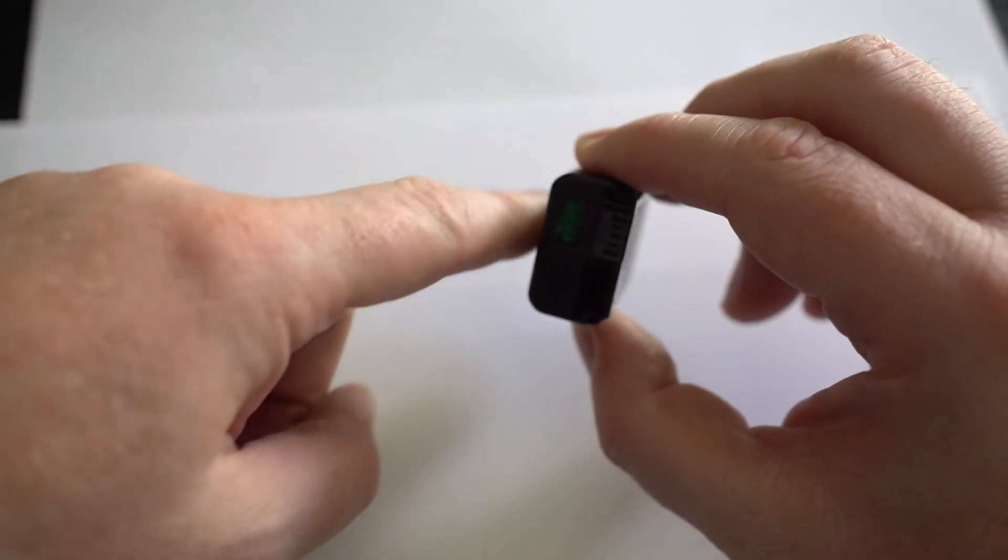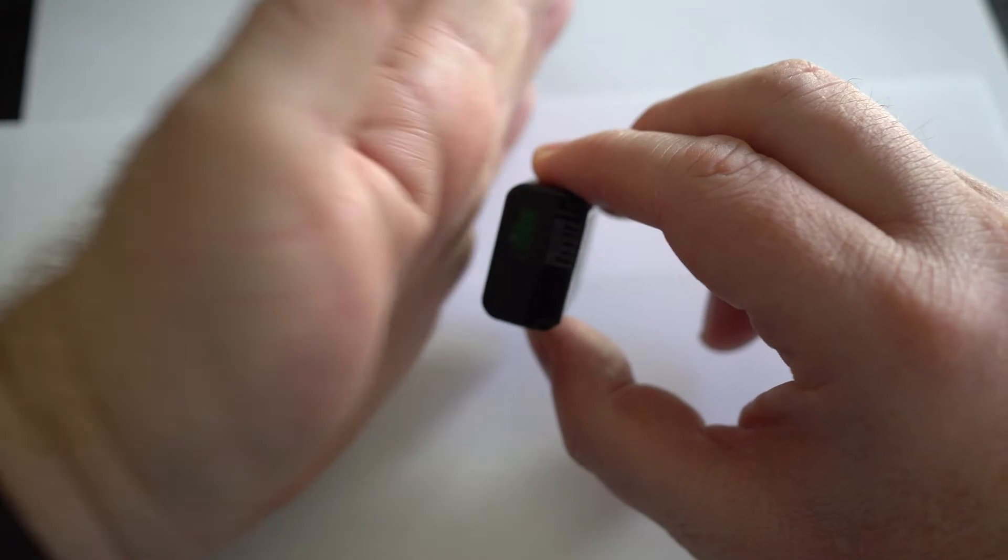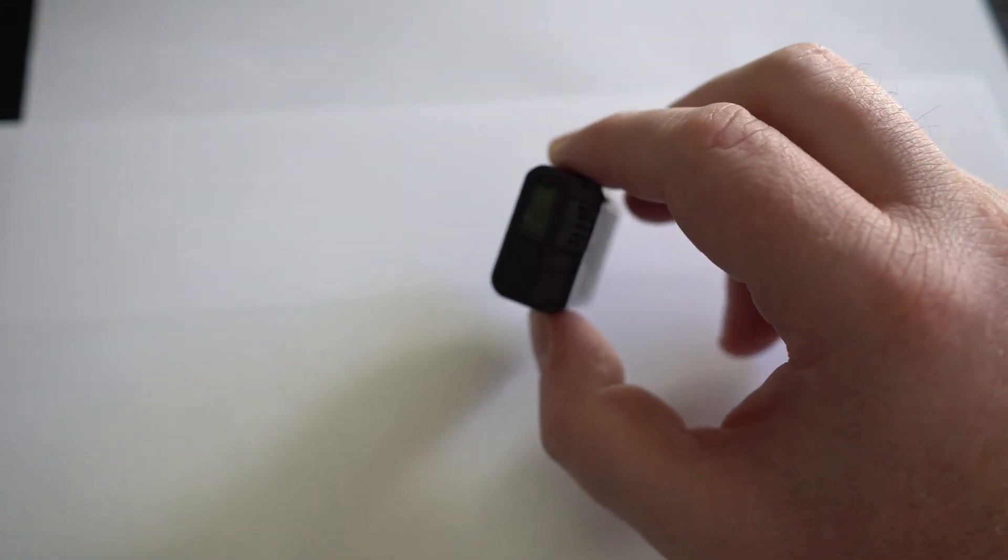Now, the good news, if we are using a dummy plug which we are going to hack up today, there's no danger of things blowing up because there's no lithium battery there. So I think the sensor is overreacting. But even then, we did some testing with dummies and it kind of overheats at the same moment. I think it has to do with the area next to the battery, if it's in the housing, probably doesn't also allow heat to escape.